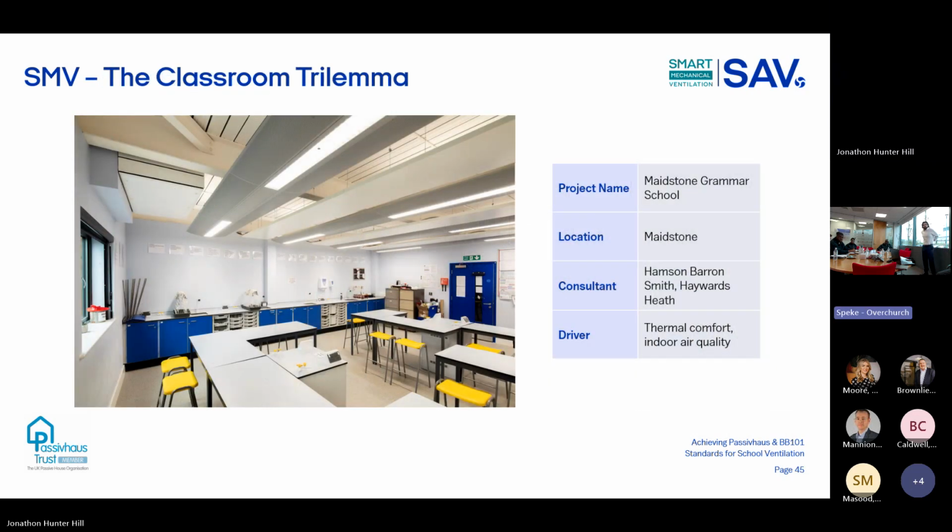This is a school that's in Maidstone. You might not be able to see it, but there's an Airmaster on the top left there. They've somehow managed to get the ceiling looking like an Airmaster. I don't know if that was intentional or not, but they had two criteria here. This is like a Georgian building, I think, and it was overheating massively. So they put in Airmaster and stripped the building back so the thermal mass was exposed. And anecdotally from that consultant, they say they've seen a huge improvement in overheating, i.e. they've massively reduced overheating in those classrooms, which is great.